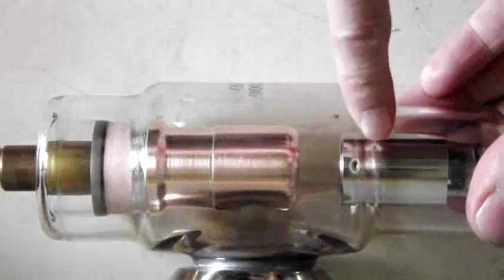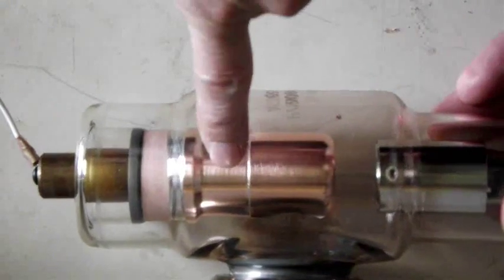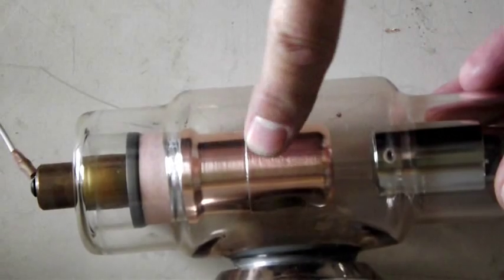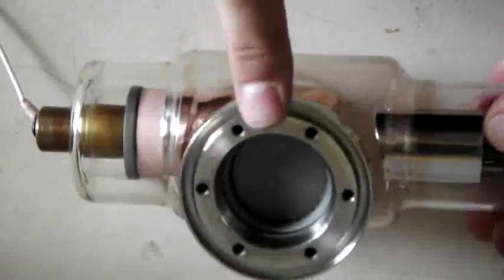This may be worth looking inside it because being this is the window where the x-rays come out and the anode's here I'm not sure how the construction would be. Normally in an x-ray tube like this one we have the heaters here and the anode here and the anode is angled so that the beam strikes the anode and the x-rays are emitted through here.